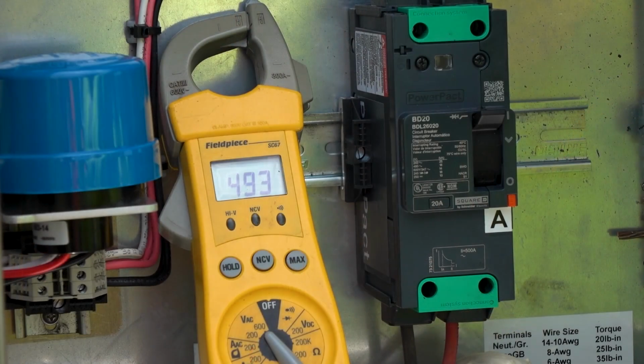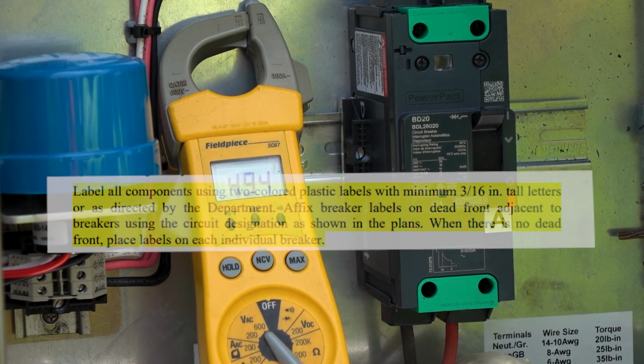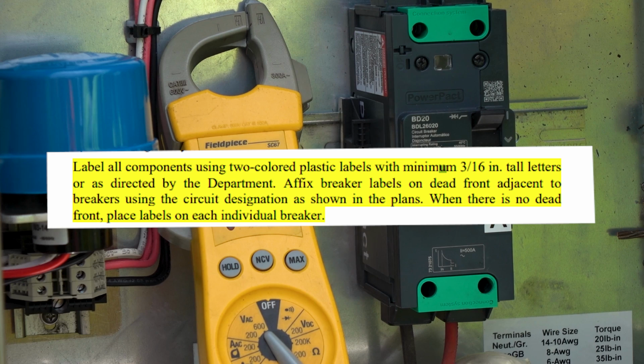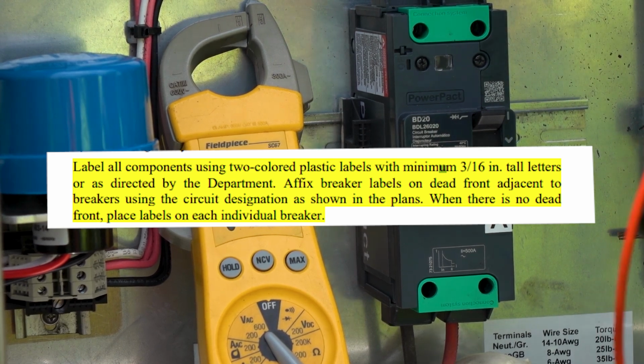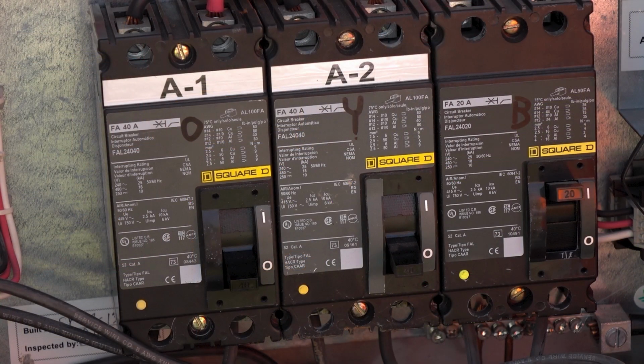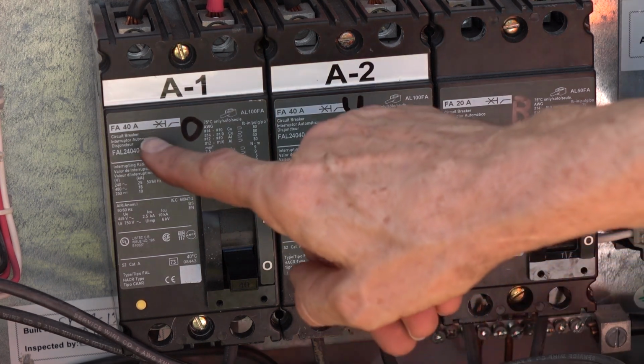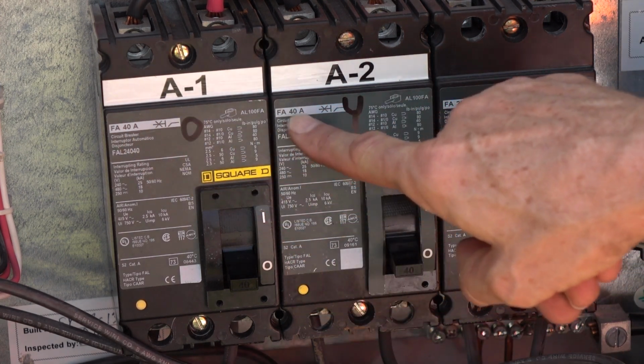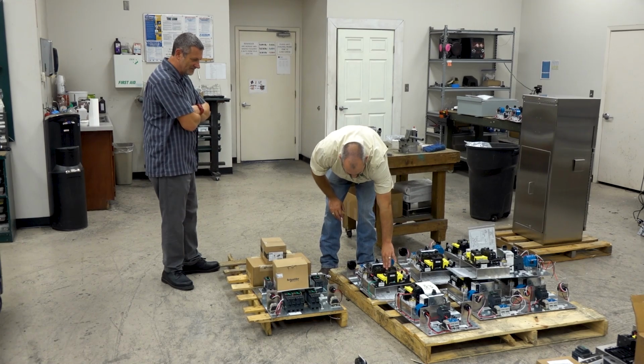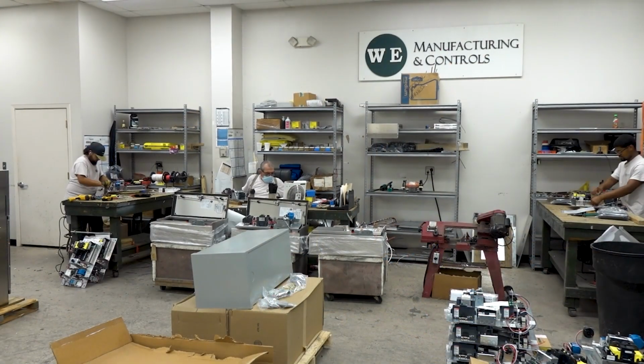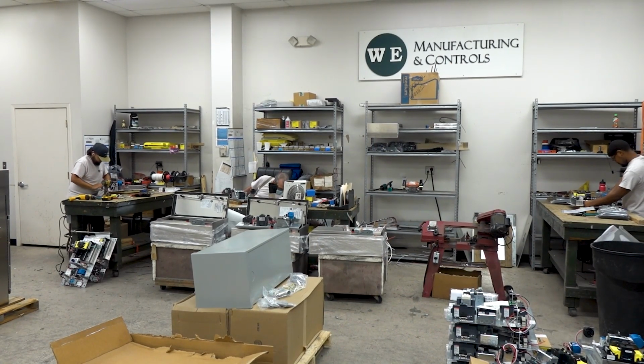The inspector's efforts are made a bit easier by TxDOT's electrical service spec DMS 11080, which requires that all electrical components within the service enclosure be labeled. The circuit breaker ampere rating is printed on the face of the breaker or on the operating handle. This makes it easy for the inspector to verify the correct size of breaker. The Type A service is required by DMS 11080 to be built only by a UL-listed industrial control panel shop.